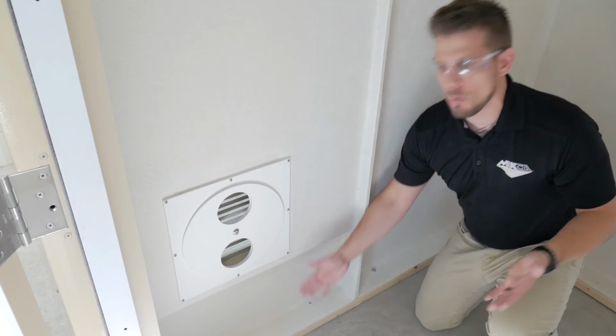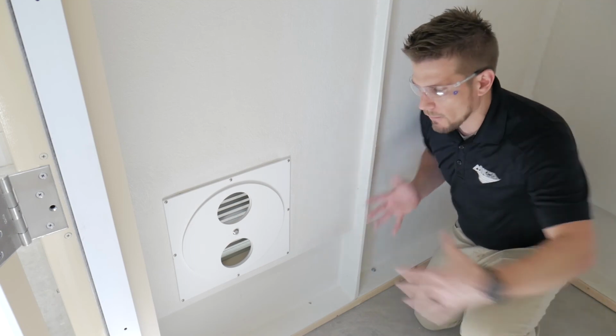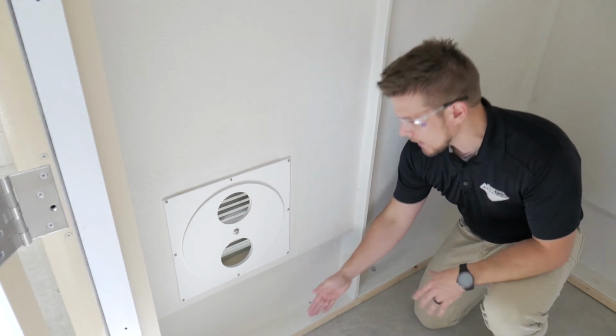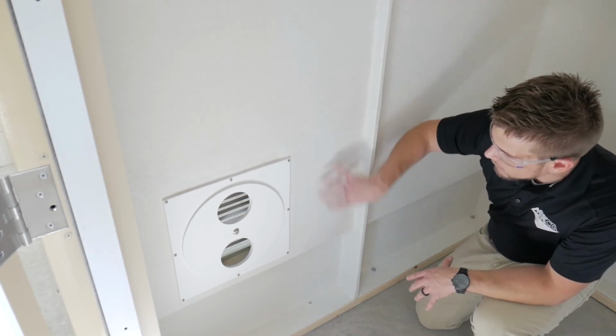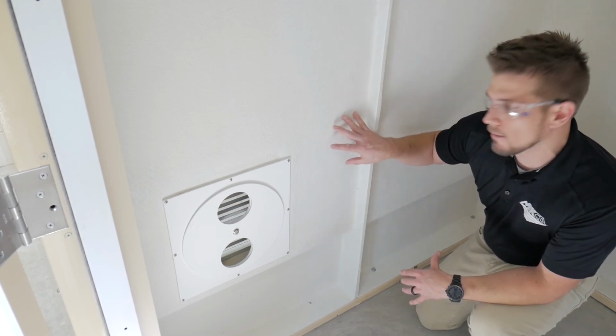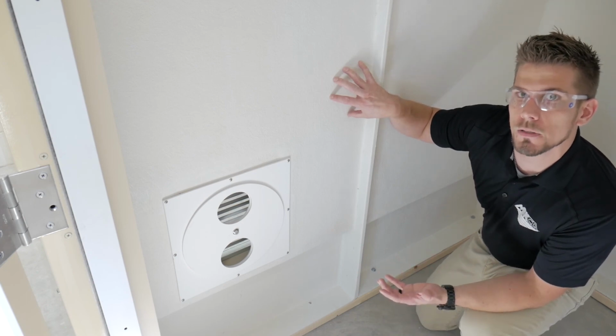Now one might say, well, why not just grow the flange? We can do that. But quite often there's a pump skid or a motor control center or something inside of this space that really inhibits that flange from growing internally. So note the transition that we are able to integrate here from a 1 inch to a 3 inch of embedded foam. This being, again, an R21 insulated building.